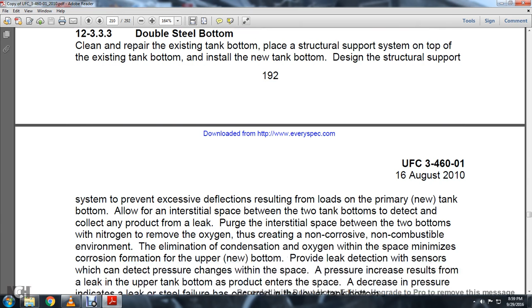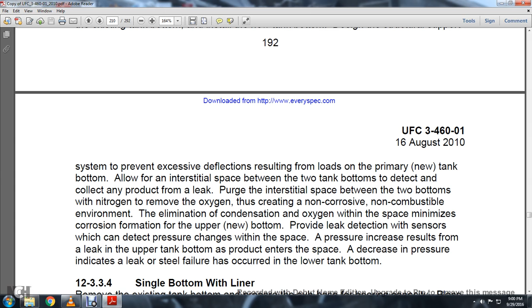Purge the interstitial space between the two bottoms with nitrogen. Remove the oxygen, creating a non-corrosive, non-combustible environment, eliminating condensation and minimizing corrosion formation on the upper and lower bottoms. Provide leak detection with sensors which can detect pressure change within the space. An increase in pressure indicates a leak of product from the upper tank within the space. A decrease in pressure indicates a leak or steel failure has occurred within the lower tank bottom.